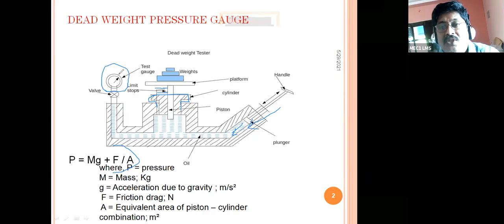Next we perform the same experiment again, but now we add the test gauge at the other end. The test gauge means we are testing whether the pressure gauge is working correctly or not. This dead weight tester is used for calibration of many pressure gauges used in different applications.